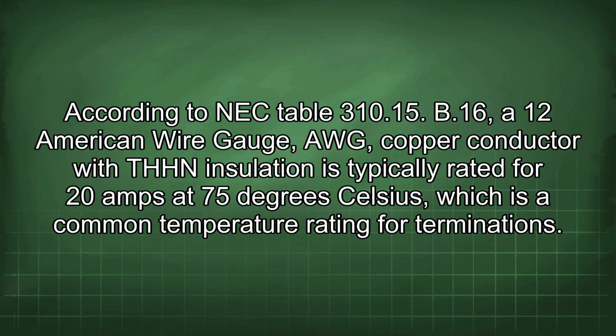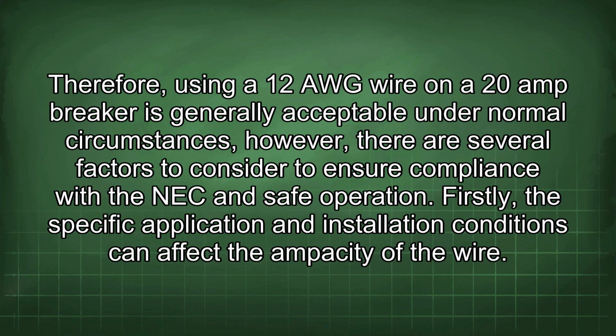According to NEC Table 310.15(B)(16), a 12 American Wire Gauge (AWG) copper conductor with THHN insulation is typically rated for 20 amps at 75 degrees Celsius, which is a common temperature rating for terminations. Therefore, using a 12 AWG wire on a 20 amp breaker is generally acceptable under normal circumstances. However, there are several factors to consider to ensure compliance with the NEC and safe operation.